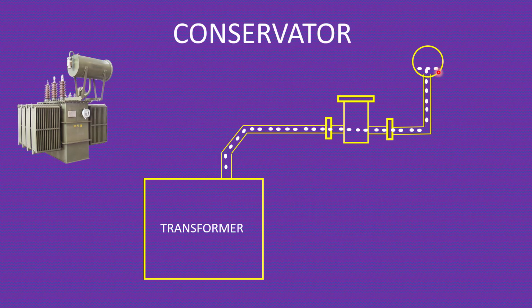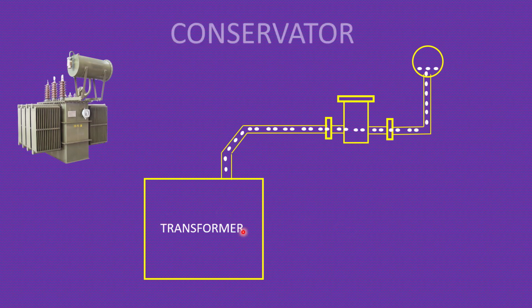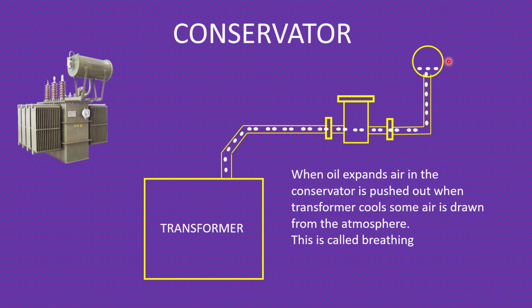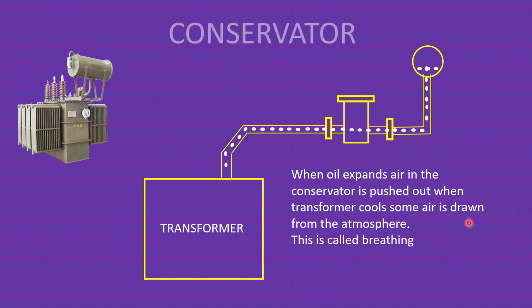What happens during operation? During operation, the oil inside the transformer will be heated and expand. This expanded oil goes to the conservator. The conservator is partially filled with oil and partially filled with air. When heating or expansion happens, the oil comes into the conservator and pushes out the air. After cooling down, or reduction of the temperature, the oil comes back to the transformer. Then some air is drawn into the conservator. When oil expands, air in the conservator is pushed out. When the transformer cools, some air is drawn from the atmosphere. So this process is called breathing.